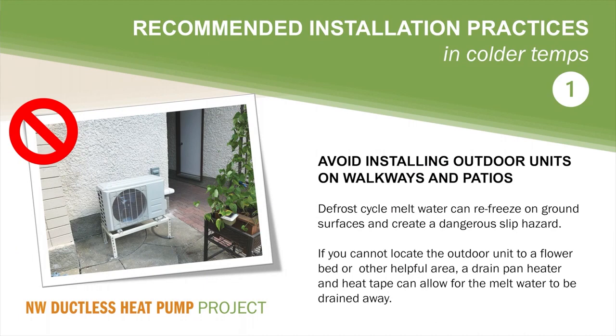The first recommendation we will cover is to avoid installing outdoor units on walkways or patios. The reason for this is that defrost cycle meltwater can refreeze on ground surfaces and create a dangerous slip hazard. If you cannot locate the outdoor unit to a flower bed or other similar area where the condensate refreeze will not be an issue, you may need to install a drain pan heater and piping to remove the meltwater.